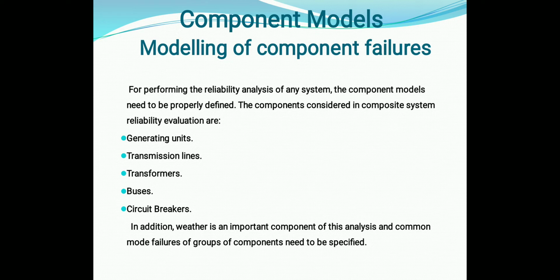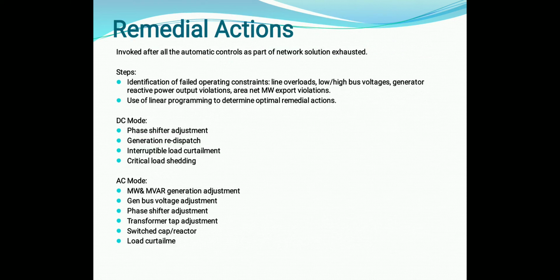In addition, weather is an important component of this analysis, and common mode failure of groups of components needs to be specified. Some remedial actions are invoked after all the automatic controls, as part of the network solution, are exhausted. Steps: identification of failed operating constraints, line overloads, low or high bus voltages, generator reactive power output violations, area net megawatt export violations, use of linear programming to determine optimal remedial actions.